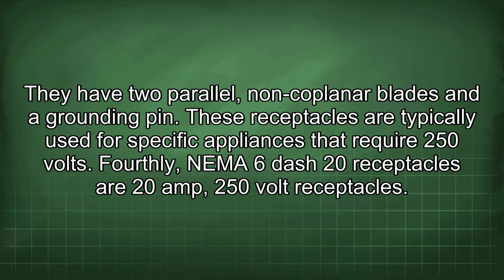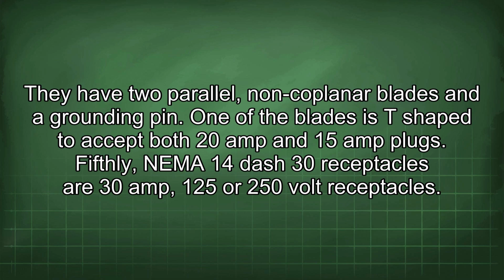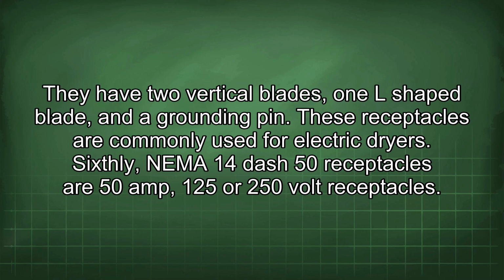Fourthly, NEMA 6-20 receptacles are 20 amp 250 volt receptacles. They have two parallel, non-coplanar blades and a grounding pin. One of the blades is T-shaped to accept both 20 amp and 15 amp plugs. Fifthly, NEMA 14-30 receptacles are 30 amp, 125 or 250 volt receptacles. They have two vertical blades, one L-shaped blade, and a grounding pin. These receptacles are commonly used for electric dryers.